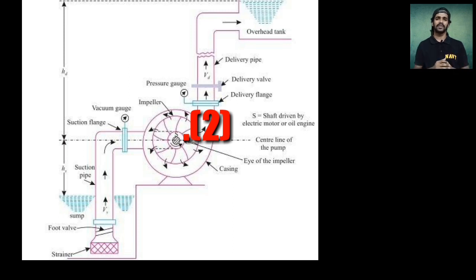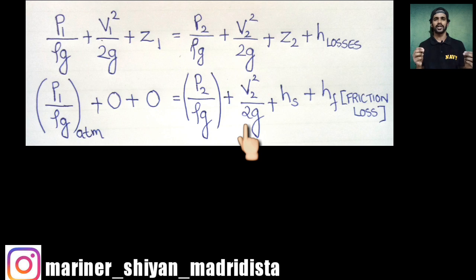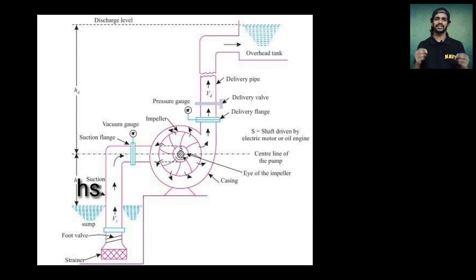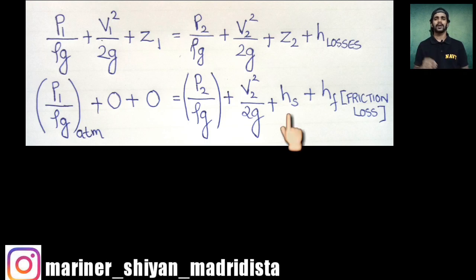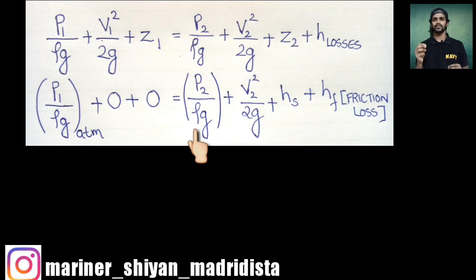On the right-hand side, considering Point 2 — the eye of the impeller — the pressure is P2/ρg. There will be a certain velocity of fluid towards the eye of the impeller, so we include V2²/2g. The suction lift from the sump towards the eye of the impeller is Hs, so Z2 = Hs. We also add friction loss, which is the dominant loss compared to eddy losses, head losses, and others — especially as flow rate increases.